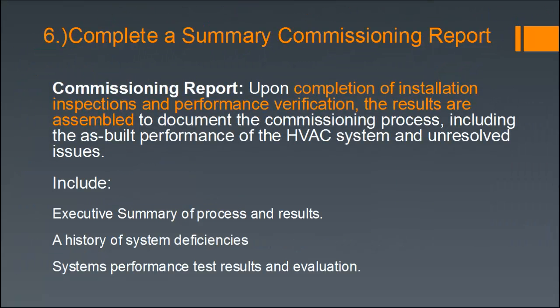You also want to complete a summary, which is the commissioning report. This is done upon completion of installation, inspections, and performance verification. The results are assembled to document the commissioning process, including the as-built performance of the HVAC system and unresolved issues. You want to include an executive summary of process and results, a history of system deficiencies, and systems performance test results and evaluation.